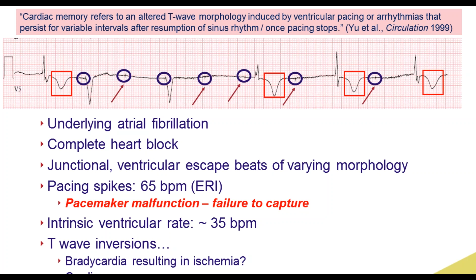The patient underwent an emergent device replacement. When the electrocautery was held over the device, it actually intermittently paced, so that was an interesting finding. The leads were disconnected and tested, and the impedance and the threshold of the leads were totally fine, so the leads were not the issue in this case. And the patient was discharged the next day, no complications.